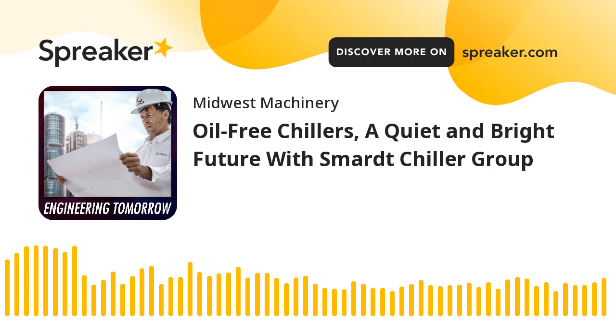One thing I'd want to comment on is you'd want to do a 10-point comparison. The reason is that with an oil-free machine, the higher efficiencies run in the 20 to 60% capacity range of the chiller. What's interesting is that in most building profiles, we design for that 1% day according to ASHRAE - but you traditionally never see it. So that machine lives its life between 20 and 60% capacity. That's where it's going to live, and that's in our wheelhouse - that's where our sweet spot is on efficiencies.